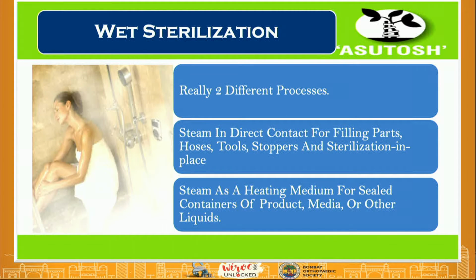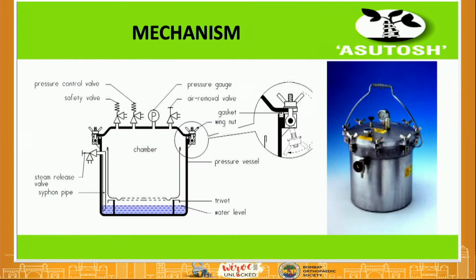Wet sterilization. Now, wet sterilization, it is steam that is used in this situation. And the steam does two things. One is it fills in the narrow cavity. Say there is a reamer, and the shaft of the reamer inside the cannulated part will be filled by the steam, and the other part will be to kill the bacteria at adequate temperatures and for adequate time.